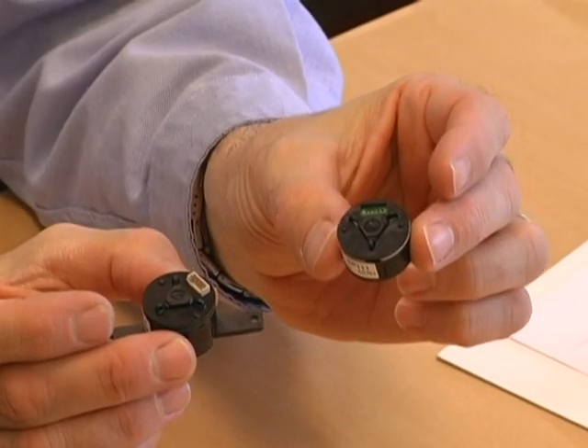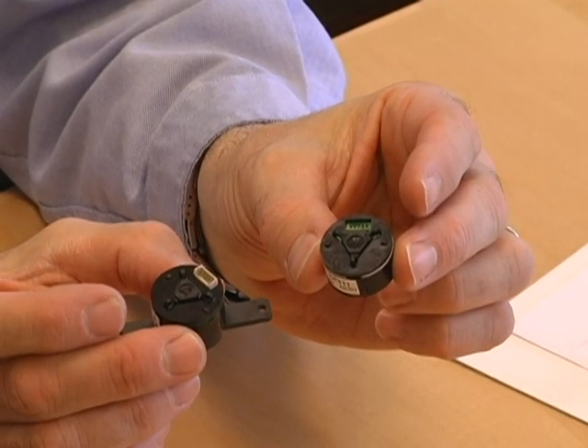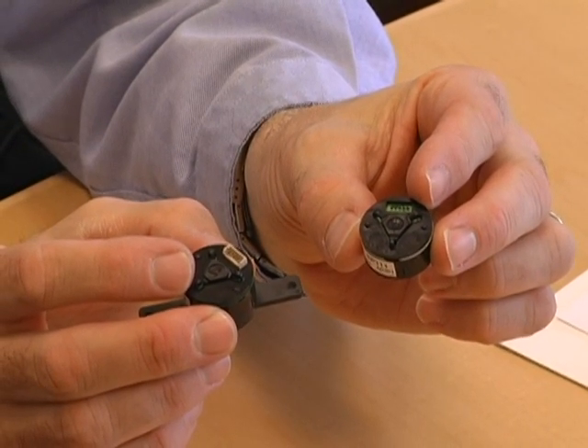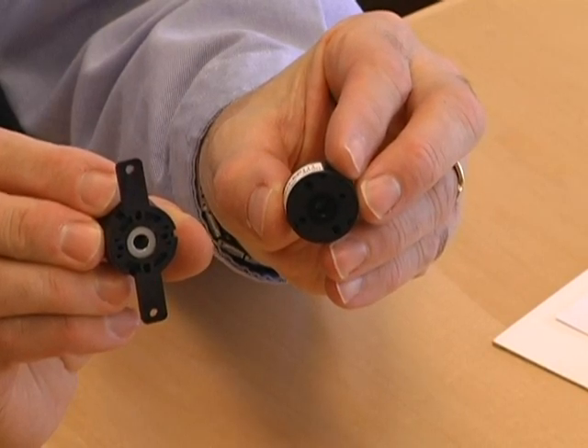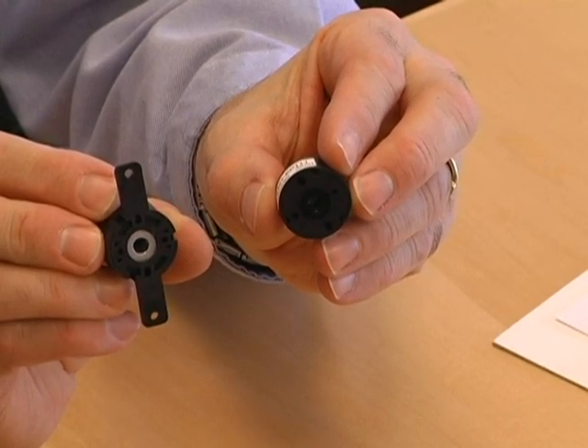Here's another family — these are reflective encoders as opposed to transmissive, and they are also incremental. This is the HEDR-5400 series. One of these is just round, so it would be mounted directly to the bottom of the motor, potentially with adhesive. Or it can be available with mounting ears if you want to mount it to a larger system. The 5400s are not quite as sophisticated as the 5500-5600s — they only go up to 200 counts per revolution and are only rated at 15 kilohertz. So they're used in much slower operating equipment, but they're smaller and a lot less expensive. For something like a vending machine where that little screw is not turning very fast, these are perfect.